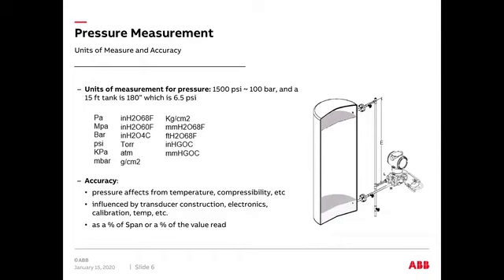The accuracy of the pressure transmitter can be affected in a lot of different ways. There's temperature effects, the compressibility of the gas or the liquid or whatever that you're measuring. The main thing that it comes from is how the transducer is constructed, the transducer that's in that transmitter, the quality of the electronics that are in it, the way that the manufacturer calibrates and characterizes the electronics with that transducer sensor. So there's a lot of different ways, and we'll talk a little more about accuracy. You'll see accuracy listed in data sheets as a percentage of the calibrated span. You may see it as a percentage of the value that's read. So those are kind of the basics of pressure measurement.